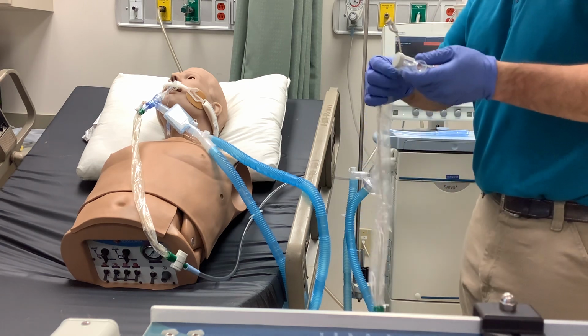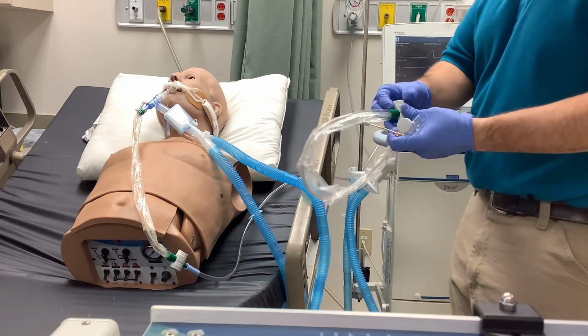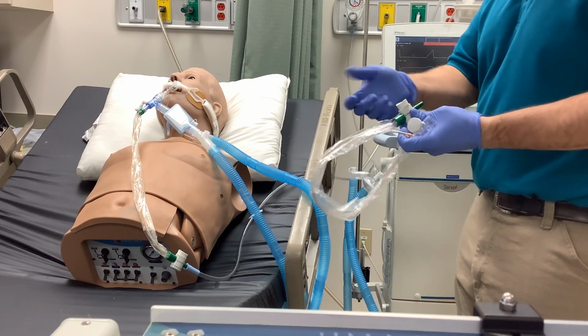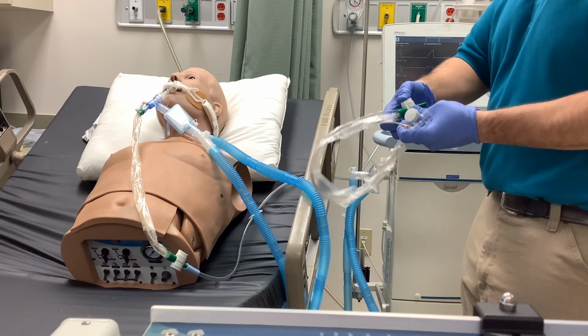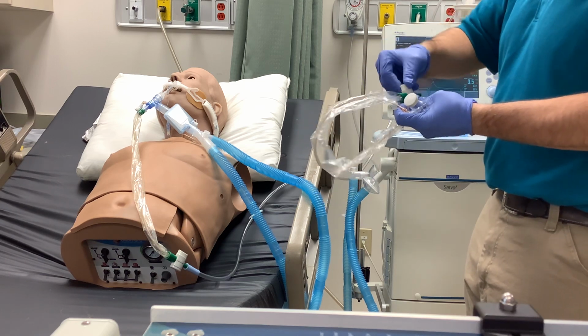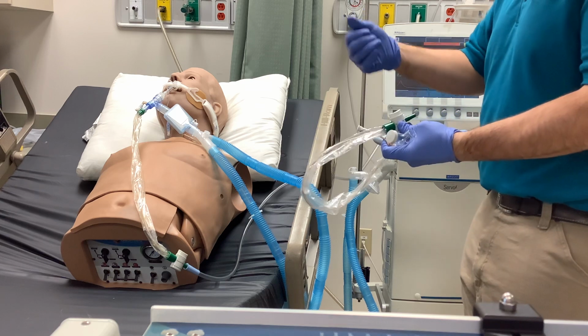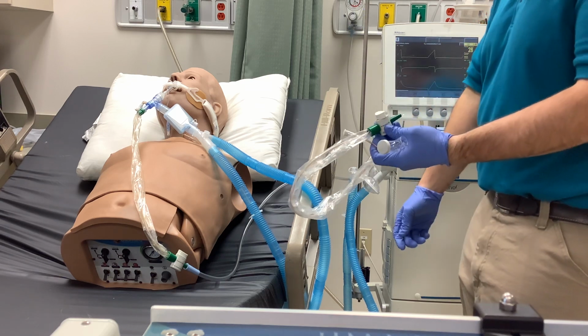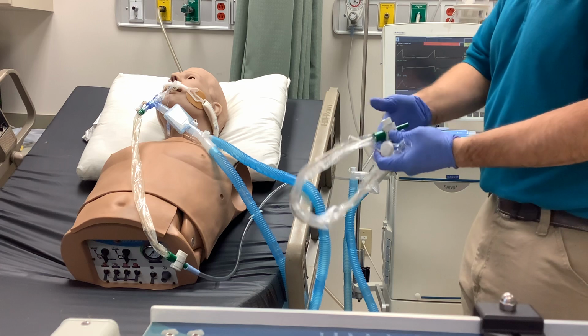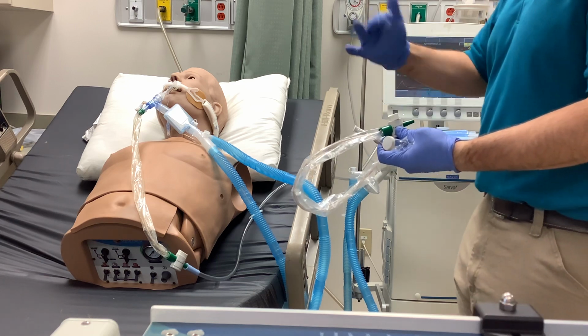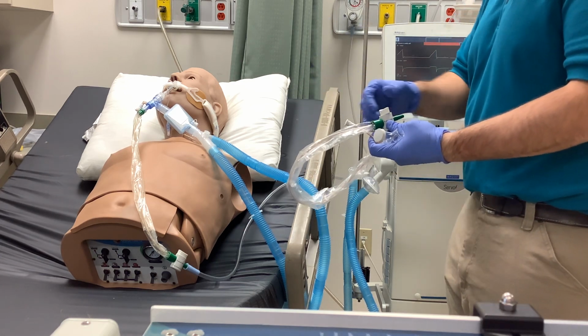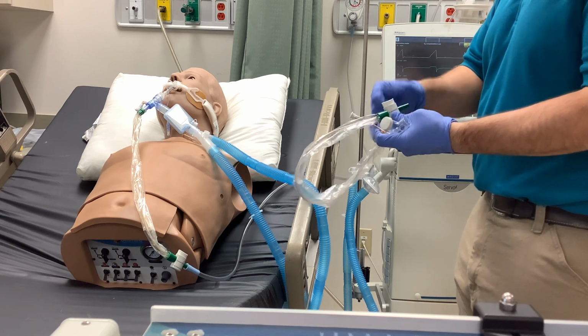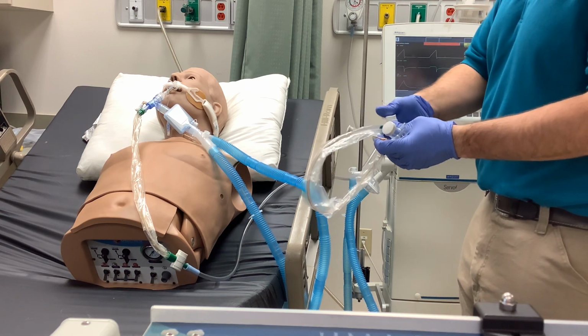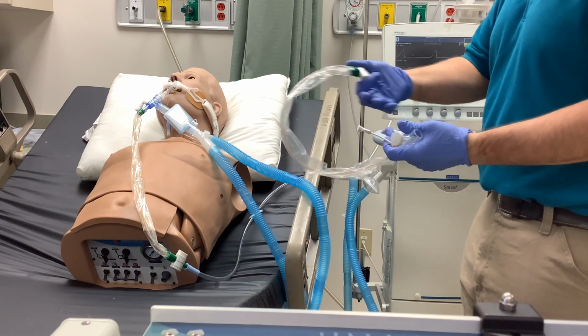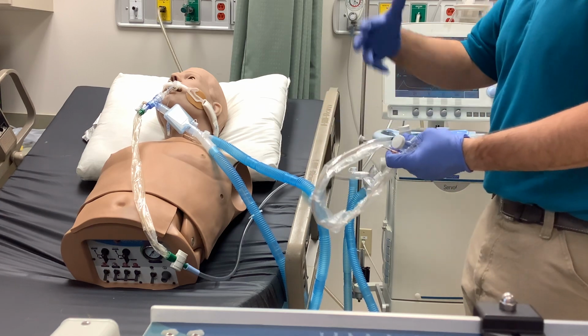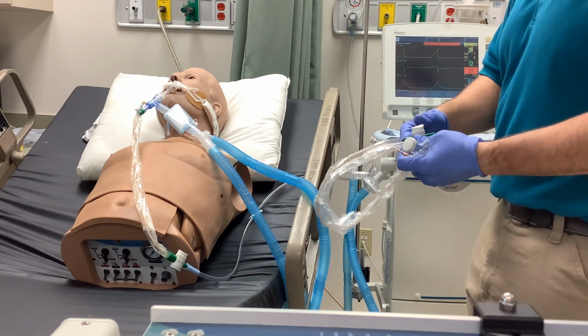Another thing as far as technique is concerned, before you suction, make sure that this port is in the unlocked position. That way you can depress it. If it's locked, you cannot depress that port. Some people have a tendency to leave it like that, which it does indeed lock it, but in the off chance that this patient happened to be in a continual lateral rotation bed or what have you, and they got moved, that could click into the unlocked position, and then if the patient rolled over on that, then you've got a vacuum going through the ventilator system, so you're going to be constantly pulling some of the air out that patient's supposed to be breathing.